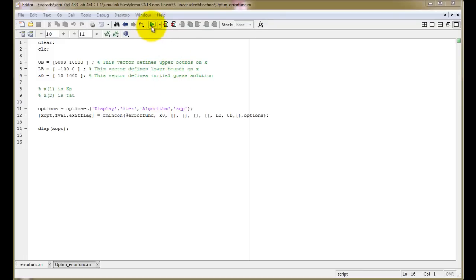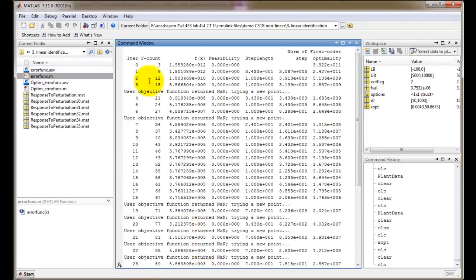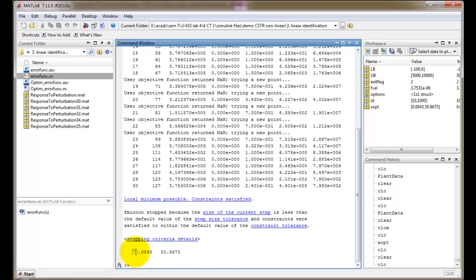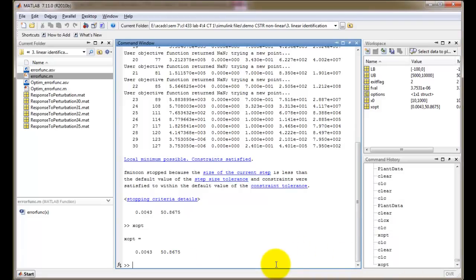Now let us run the optim_error_func.m script by clicking the green run button. The script completes its run; we can see each iteration output, and we get xopt equal to two values. The first value of xopt is Kp and the second is tau for the system. We run optim_error_func for different response_to_perturbation files to get separate Kp and tau values, then take an average of the Kp and tau values to use for our system.